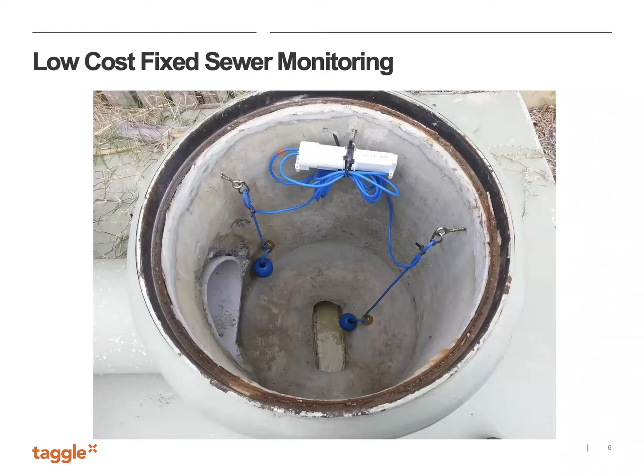So as a first generation device, these work reasonably well, although we did discover that sewer networks are quite turbulent environments. Let me describe how this is supposed to work, and then I'll talk a little bit about the limitations. So those float switches operate by, as the fluid level in the manhole rises, the float switch lifts and triggers a switch, either a mercury switch or a little ball bearing oriented switch, that tells you that the float has now inverted and that there's now water at that level.